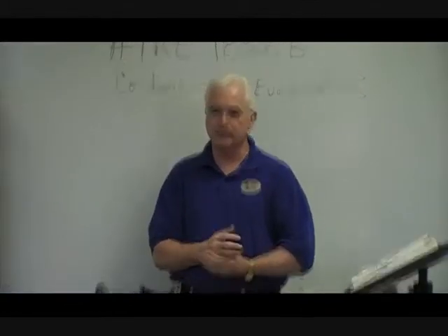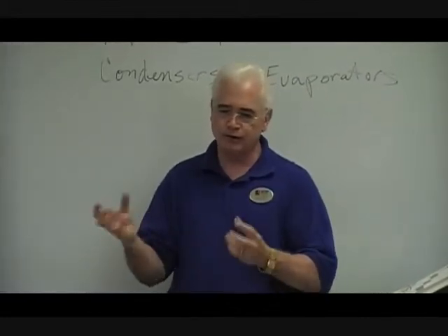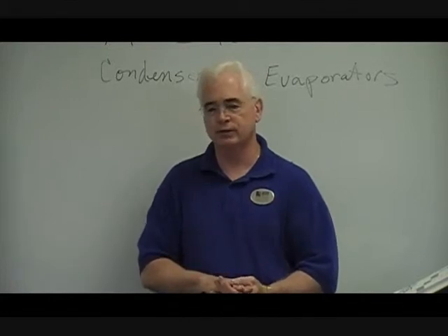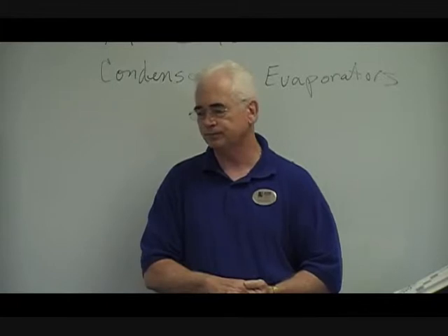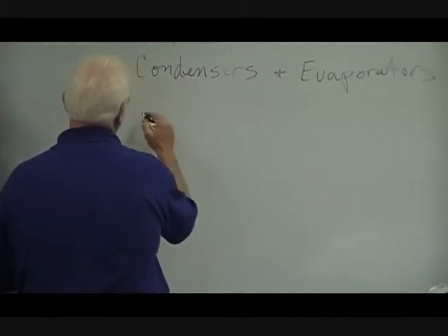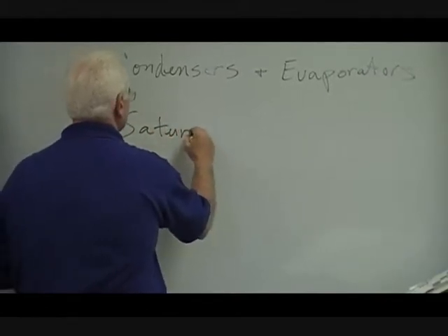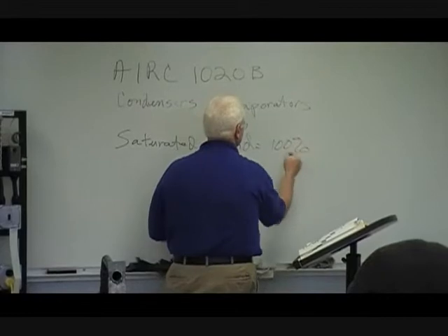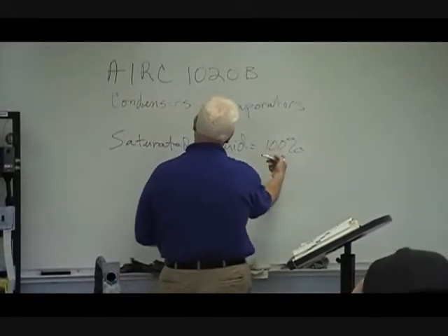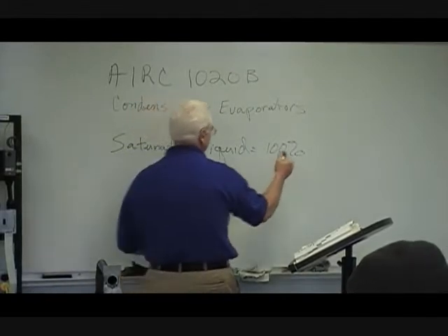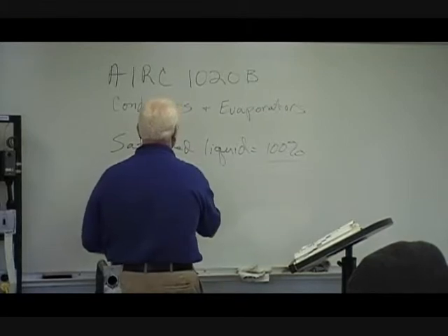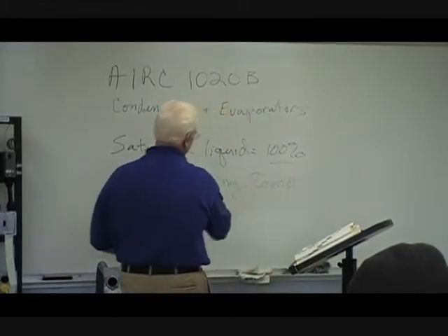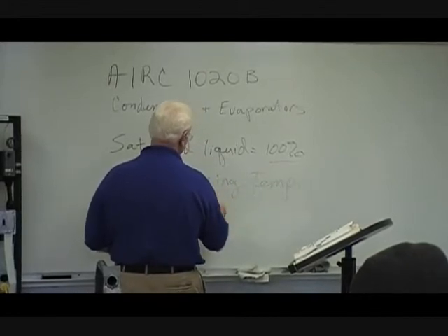What does the term saturated liquid mean? That's the point in the condenser where there's no more vapor to condense. It's 100% liquid. The temperature of that liquid corresponds to your pressure in the condenser, and that's also known as your condensing temperature. So that's very important. What's the term that we called it? Saturated liquid. That's when the liquid in the condenser is 100% liquid and it corresponds to your condensing temperature. Okay, the condensing temperature corresponds to your pressure, or your high side pressure.